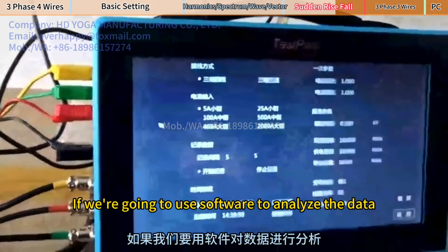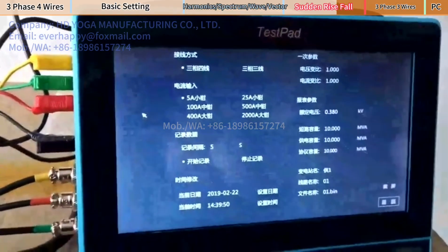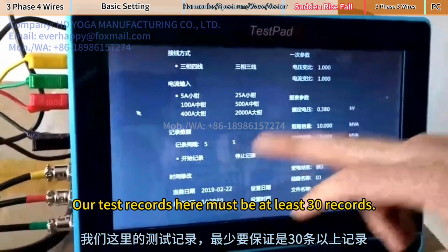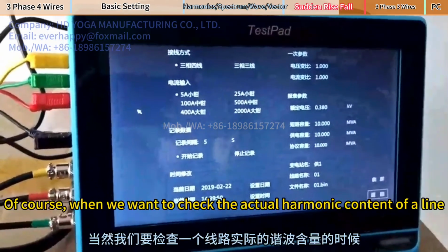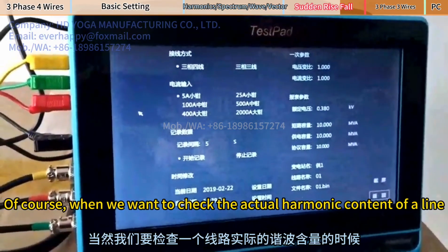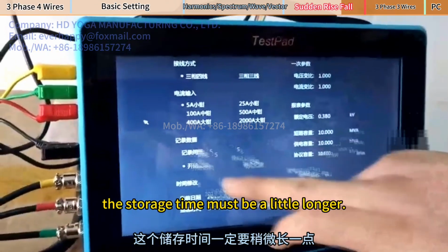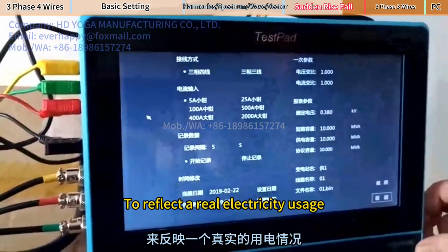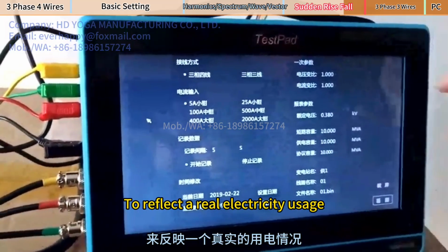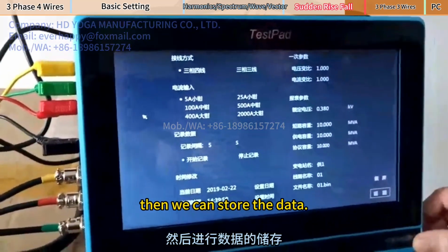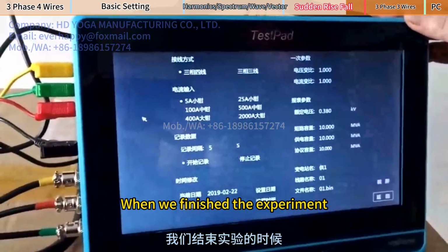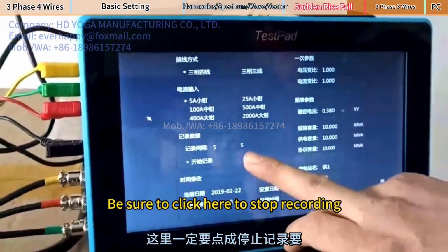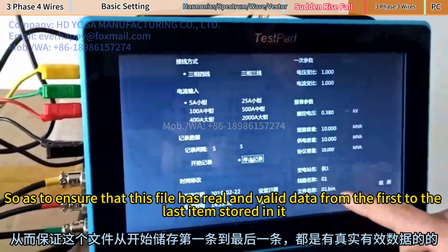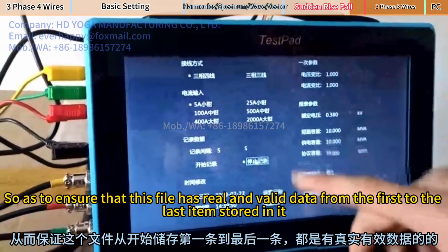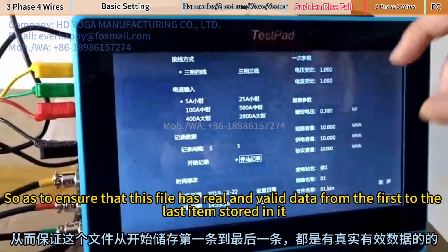If we're going to use software to analyze the data, our test records here must be at least 30 records. Of course, when we want to check the actual harmonic content of a line, the storage time must be a little longer, to reflect a real electricity usage. Then we can store the data. When we finished the experiment, be sure to click here to stop recording, so as to ensure that this file has real and valid data from the first to the last item stored in it.